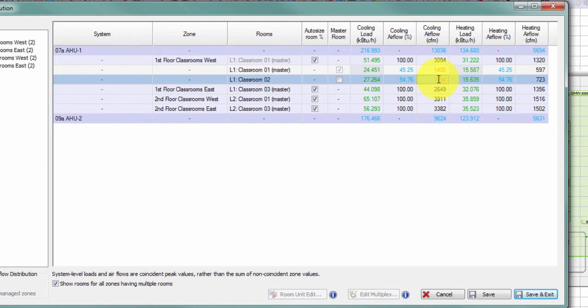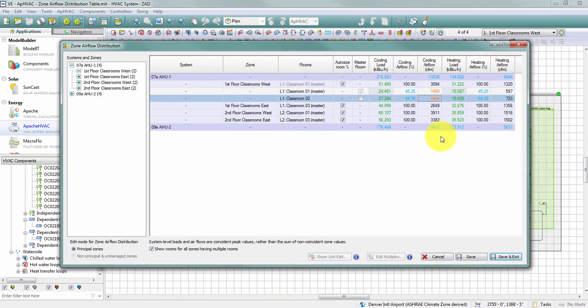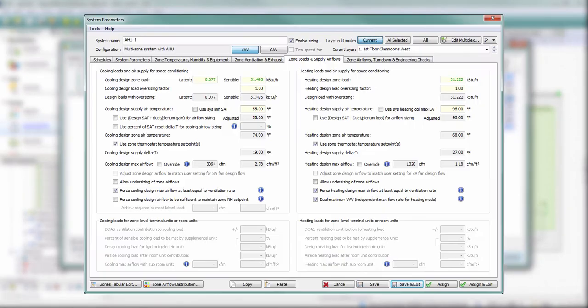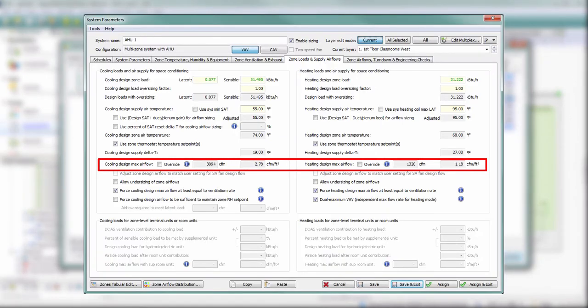If I want to edit the airflow to the zone itself — the 3094 CFM in my example — that needs to be done outside of this table. This table is only for distributing the zone's airflow among the spaces within it. To change the heating or cooling airflow supply to the zone, use the override options on the Zone Loads and Supply Airflows tab in the System Parameters dialog.